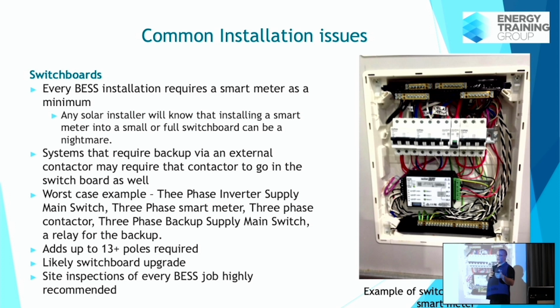On a three-phase site, I might have 3 poles of main switch, 3 poles of backup supply main switch, 4 poles of 3-phase smart meter. I'm up to 12 or 13 poles in a switchboard so I can install a 3-phase backup system for a customer. How many people have 14 poles spare in their switchboard? Almost nobody, so usually you're going to be doing some sort of switchboard upgrade.